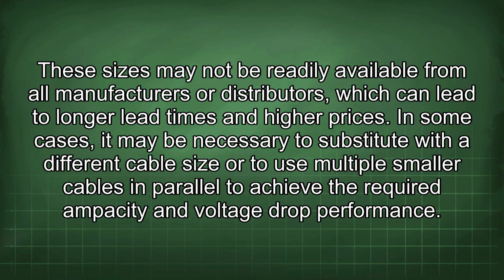Availability can also be a limiting factor when considering the use of 300kcmil and 600kcmil cables. These sizes may not be readily available from all manufacturers or distributors, which can lead to longer lead times and higher prices. In some cases, it may be necessary to substitute with a different cable size or to use multiple smaller cables in parallel to achieve the required ampacity and voltage drop performance.